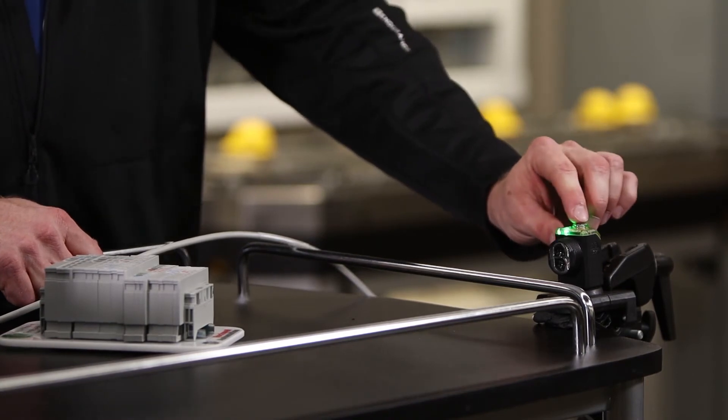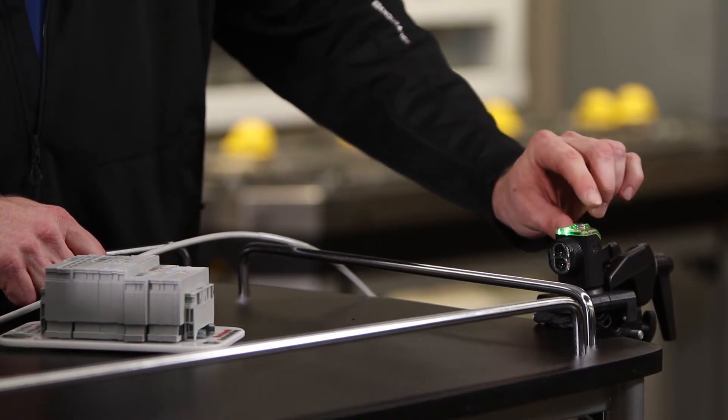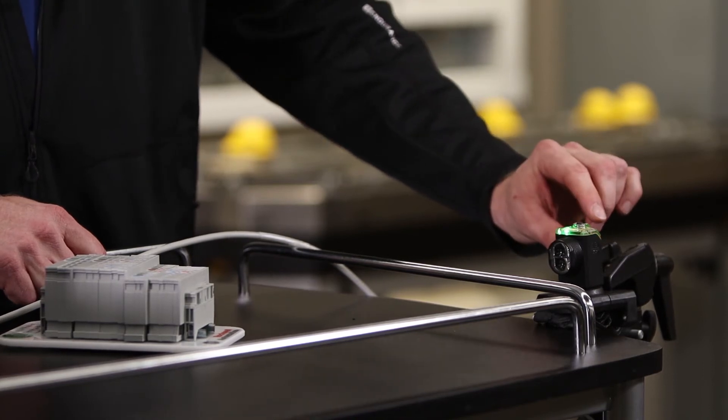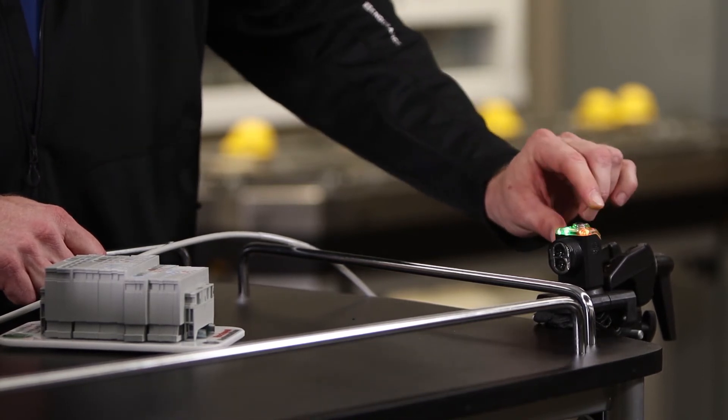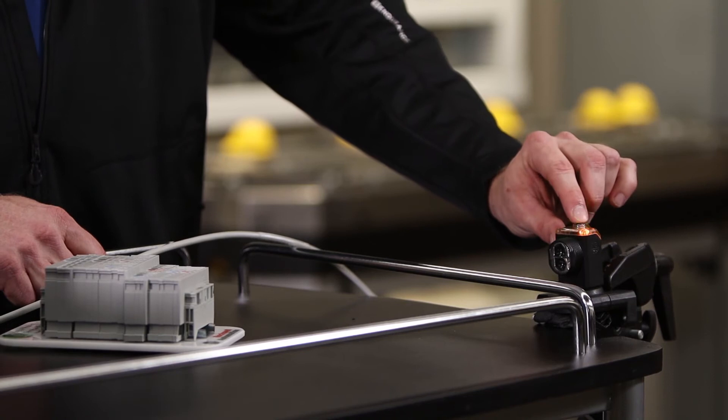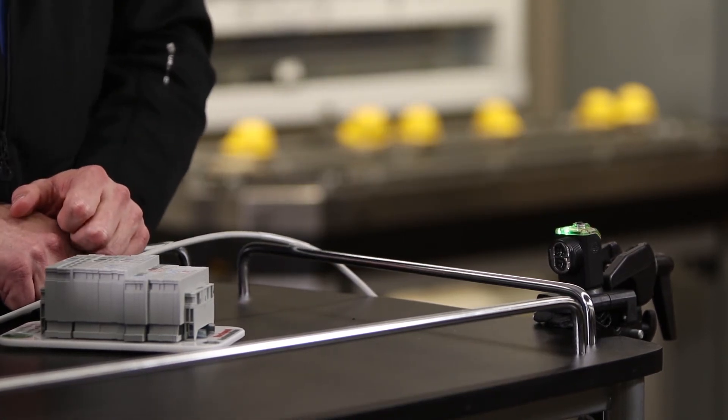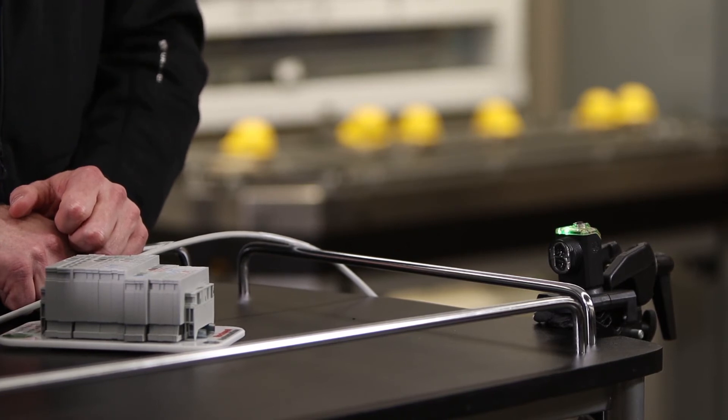You can now toggle between light and dark by pressing and releasing the button. When the orange LED is on, you are in light operate. When the orange LED is off, you are in dark operate. The sensor will save the last setting after 10 seconds of inaction. So once you have it set, leave it be for 10 seconds and the sensor will go back to run mode.